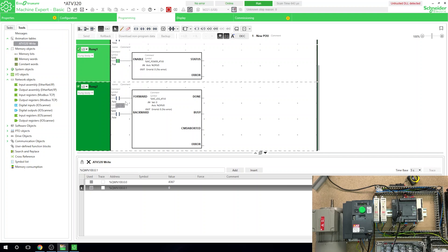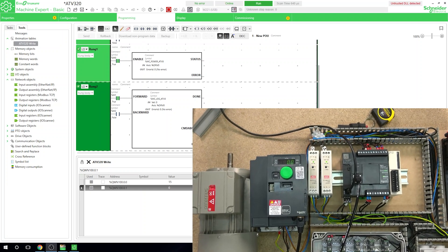Let's load that in — PC to controller. Enable the drive and put it into run mode. You can see the drive is showing zero frequency — it's saying it doesn't have a frequency yet and doesn't know where to go. The values in the output word are changing as the bits are activated. I'll leave a manual in the description below for bit mapping if you want to read up on it. As you can see, the enable run forward bit is bit 15.